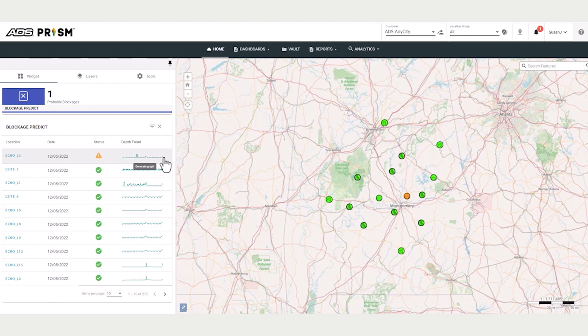PRISM compares that pattern to a library of thousands of cases of blockage patterns. If the location is a flow meter, the velocity data is also reviewed. PRISM can discern between wet weather increases versus developing blockage patterns.